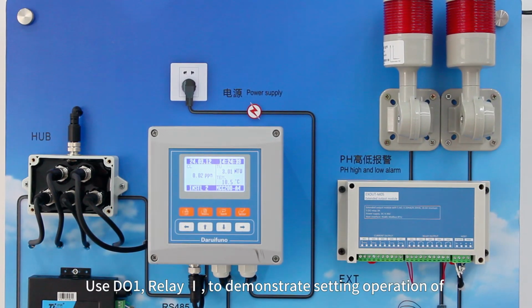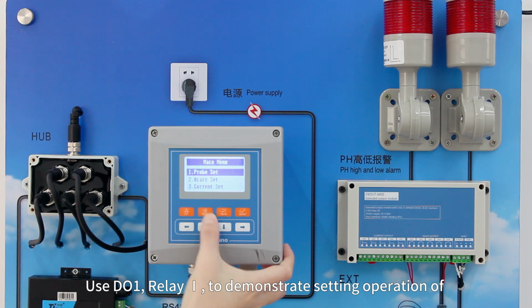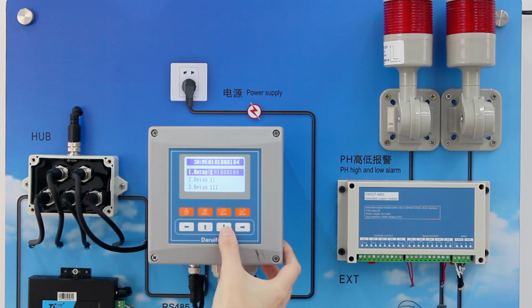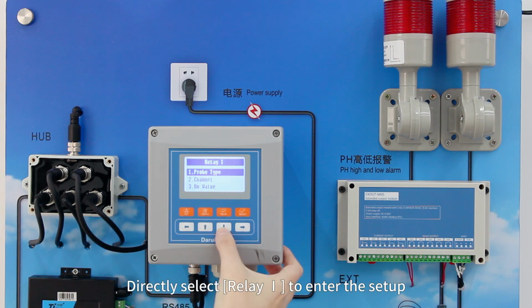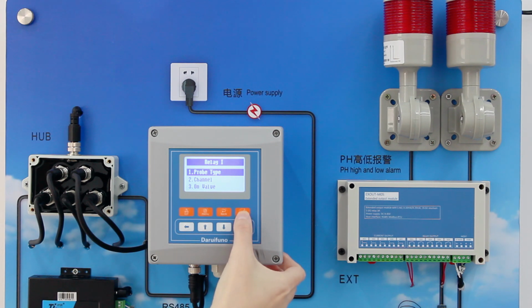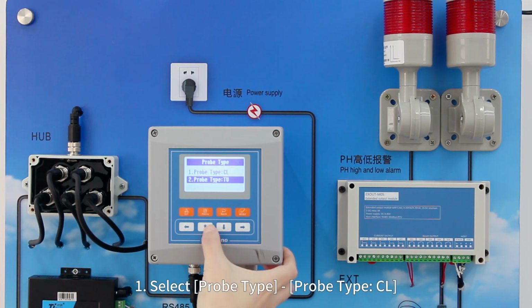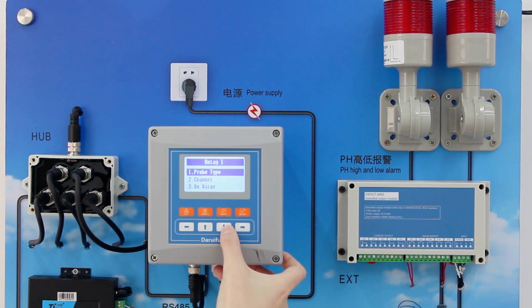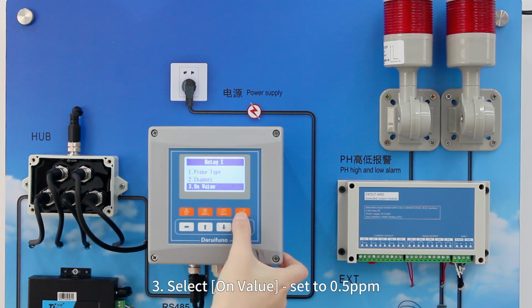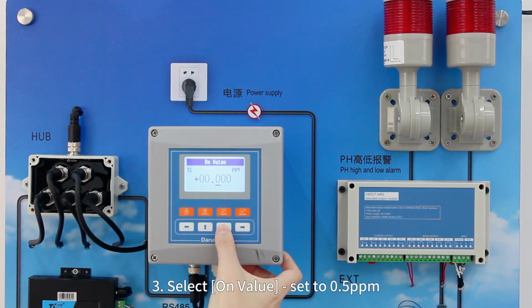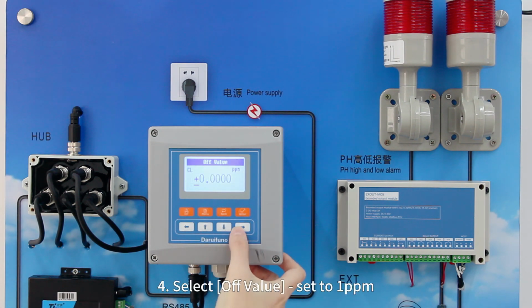Use DO1, Relay 1, to demonstrate the setting operation of the residual chlorine dosing pump. Directly select Relay 1 to enter the setup. Select Probe Type, CL. Select Channel, CL. Select On Value, set to 0.5 ppm. Select Off Value, set to 1 ppm.